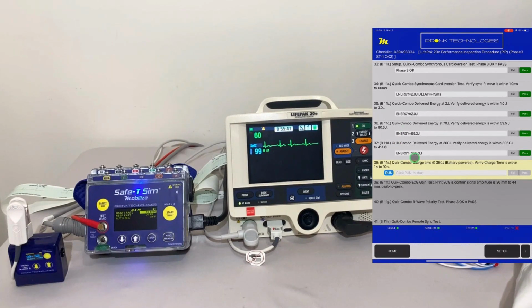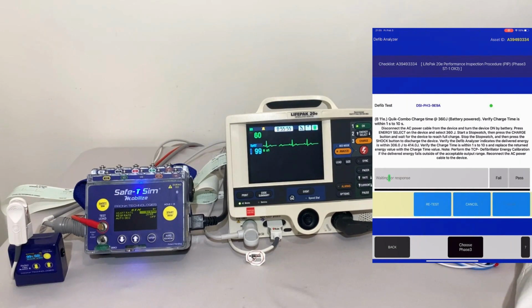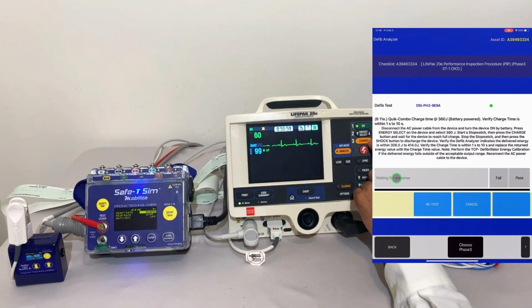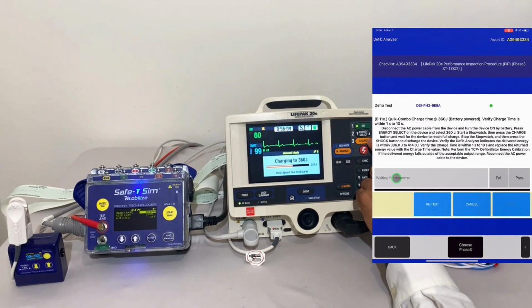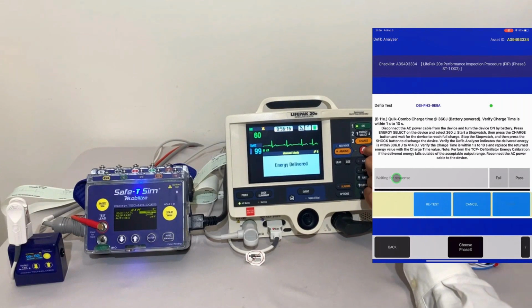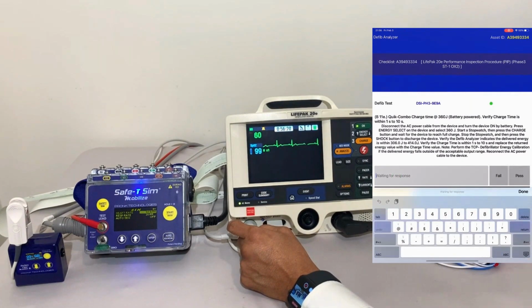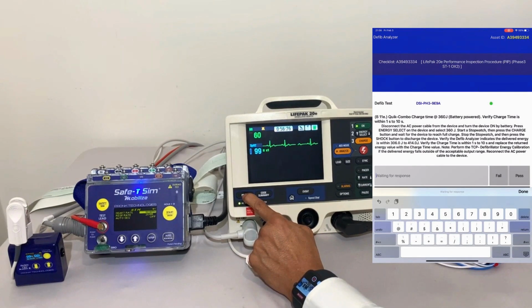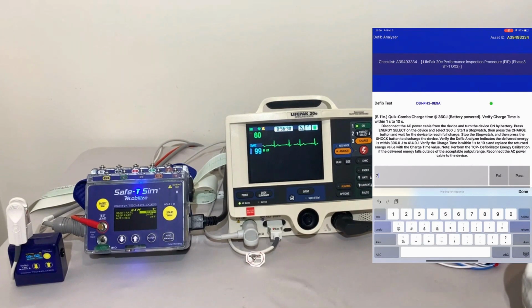So now we want to make sure we do all of the remaining tests, including the quick combo charge time test. This is a time test to verify that the charge time of the defibrillator is within specifications. So it's a 1 to 10 second run test, and we're going to make sure that the defibrillator does that using a calibrated stopwatch. We're going to go ahead and start charging and start the stopwatch at the same time and verify how long it takes. It should occur within 10 seconds. Within 7 seconds. Go ahead and document that. Occur within 7 seconds. Let's go ahead and do that here. We've got the energy result, but this is a time test, so we'll go ahead and type in 7 seconds and make sure we capture it into our report.